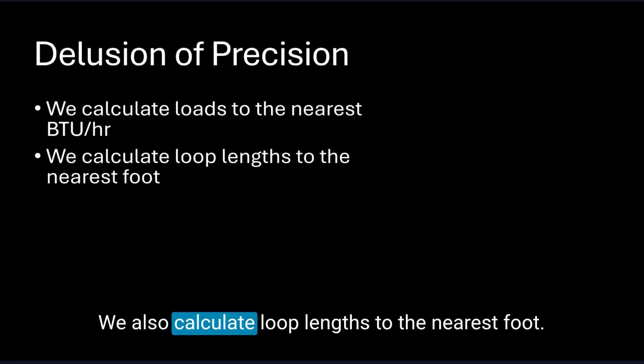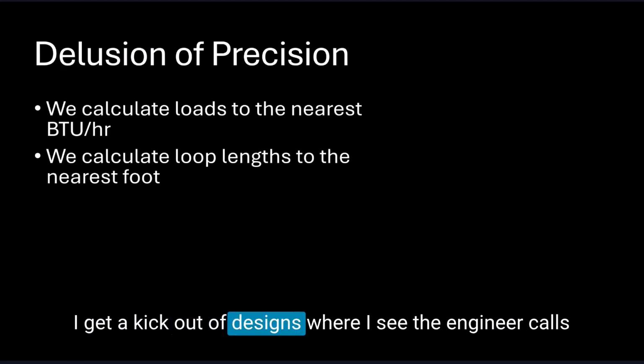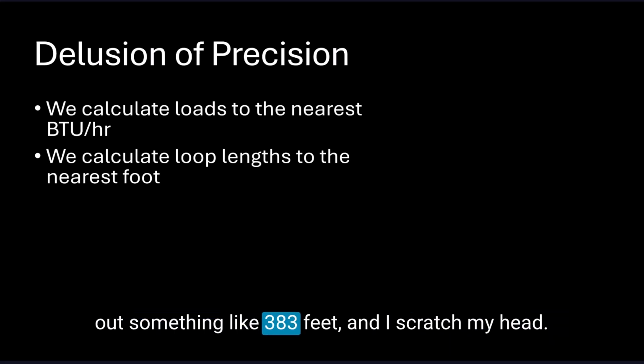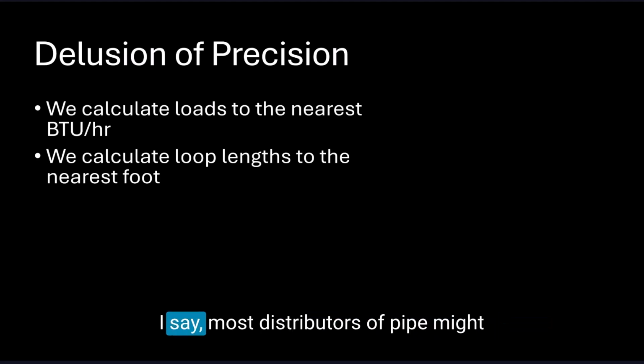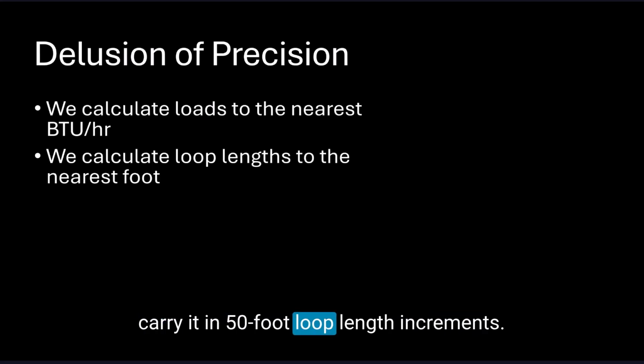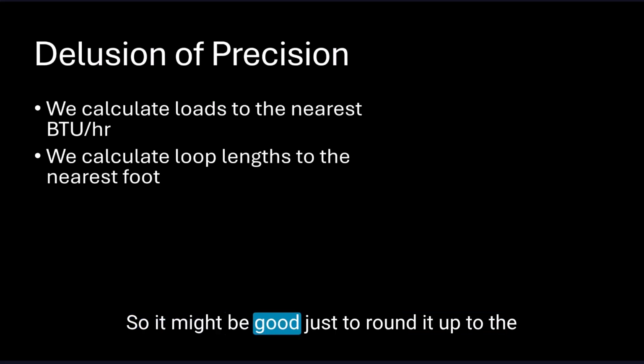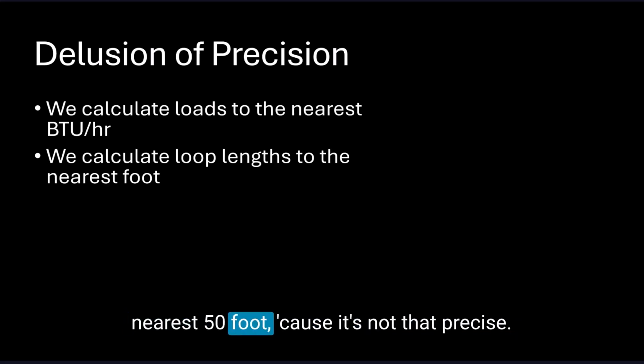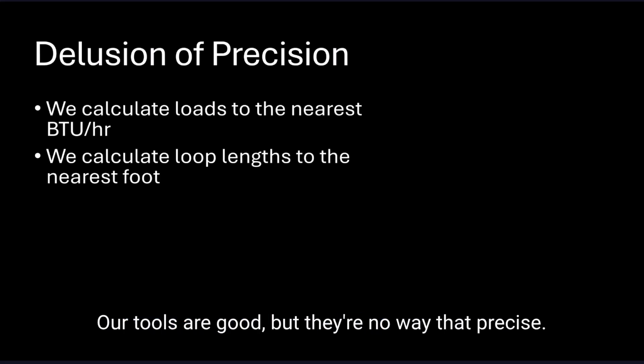We also calculate loop lengths to the nearest foot. I get a kick out of designs where I see the engineer calls out something like 383 feet, and I scratch my head. I say, most distributors of pipe might carry it in 50-foot loop length increments. So it might be good just to round it up to the nearest 50 foot because it's not that precise. Our tools are good, but they're no way that precise.